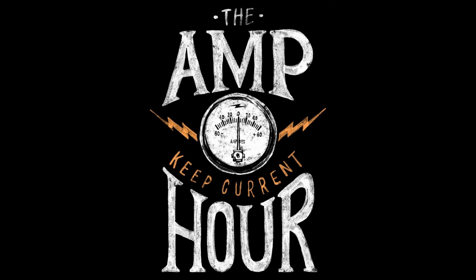Yeah. And the interesting thing is that we've gotten some questions that, okay, but I'm powering it from my 5-volt USB. Yeah, it doesn't really matter because there is an isolated power supply inside that will generate plus minus 30 volts. Yeah, it'll get there at all times. It's just current limited, not voltage limited, right?